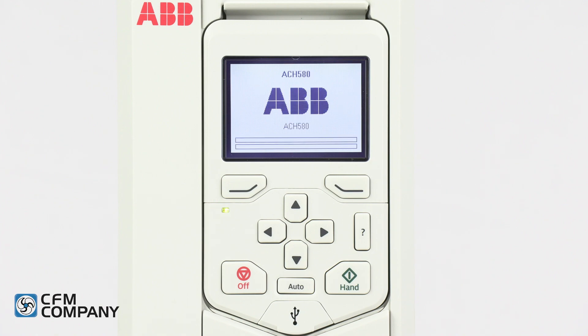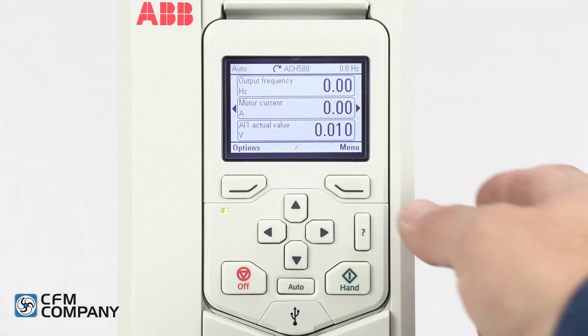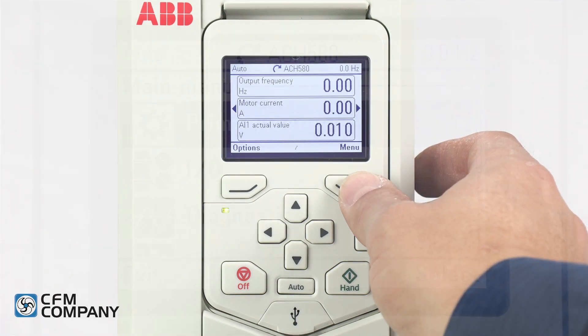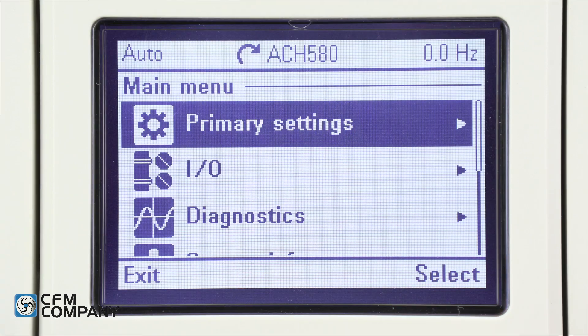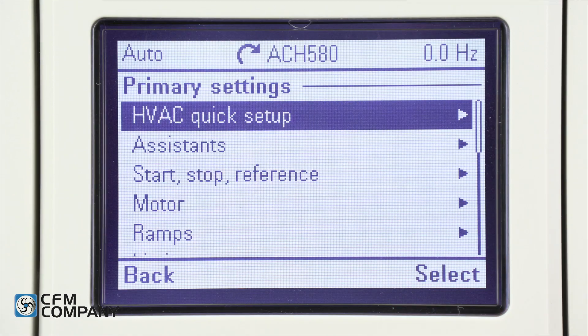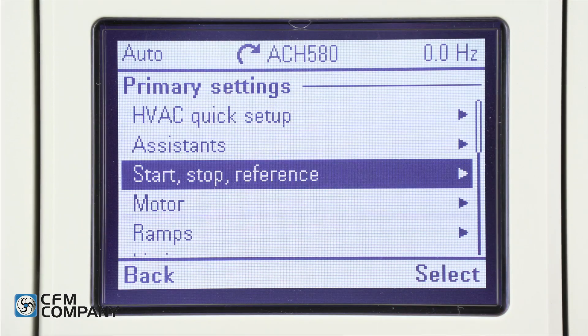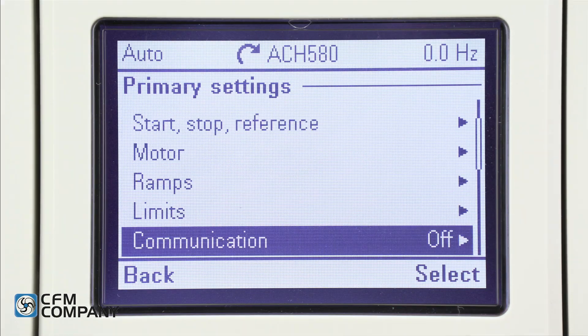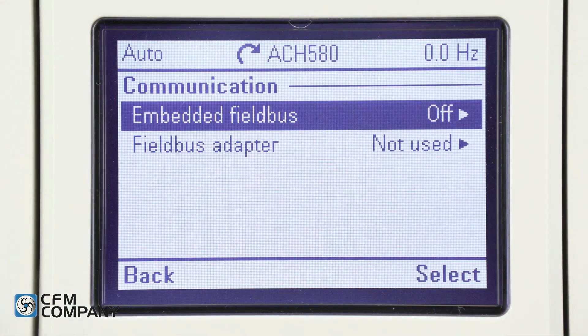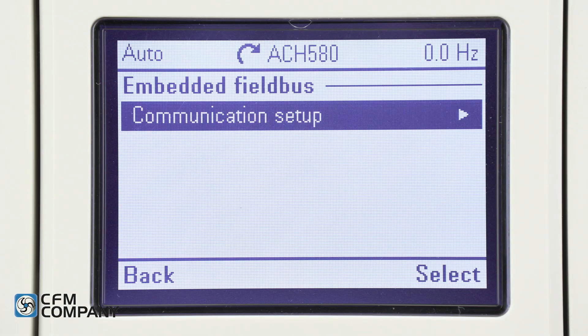Once the communication wires are landed, secure the drive cover and apply power to the drive. From the home screen, press menu, select primary settings, arrow down to communication, press select. Select embedded field bus, then select communication setup.